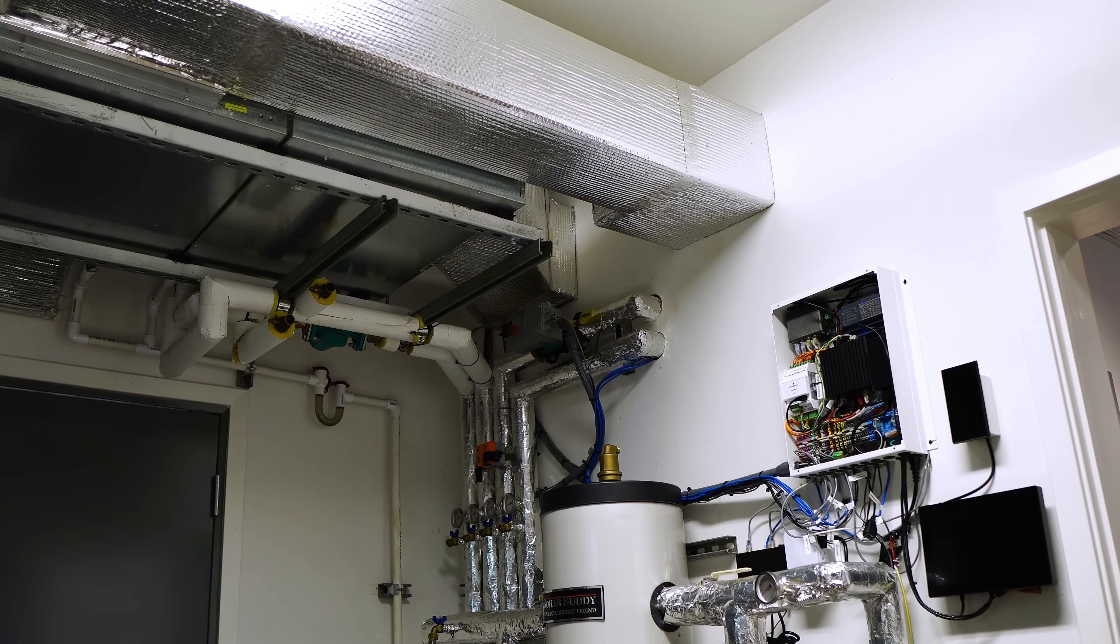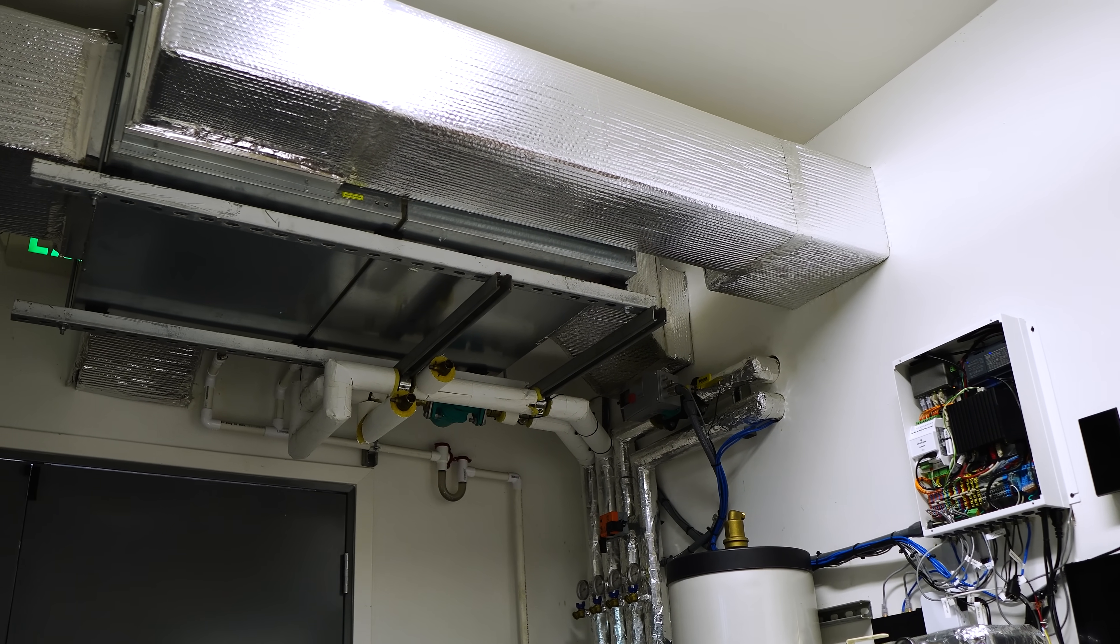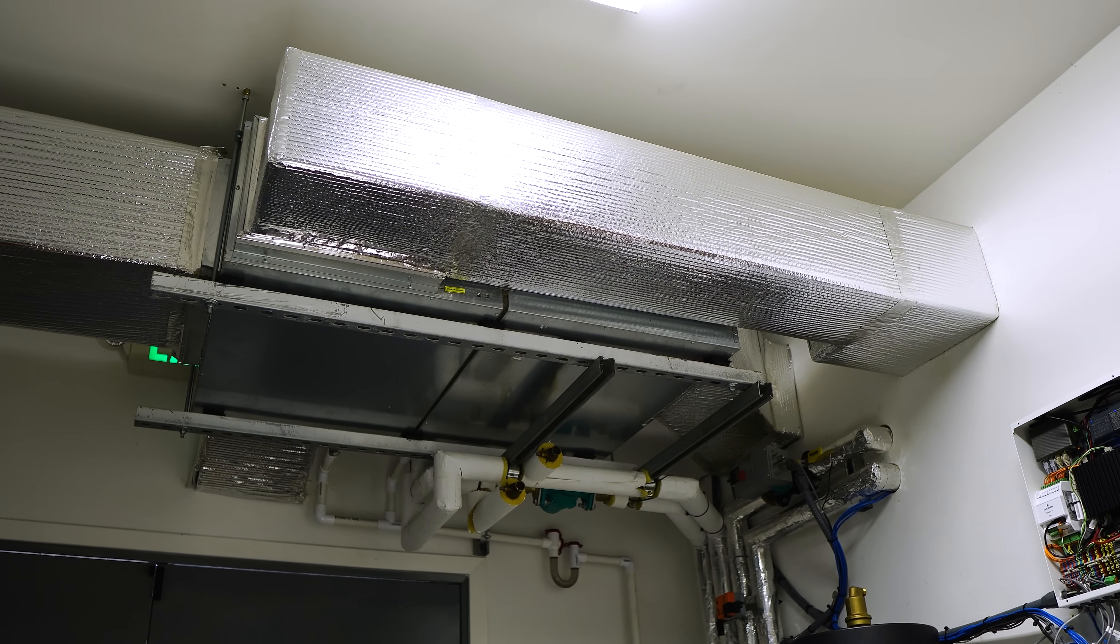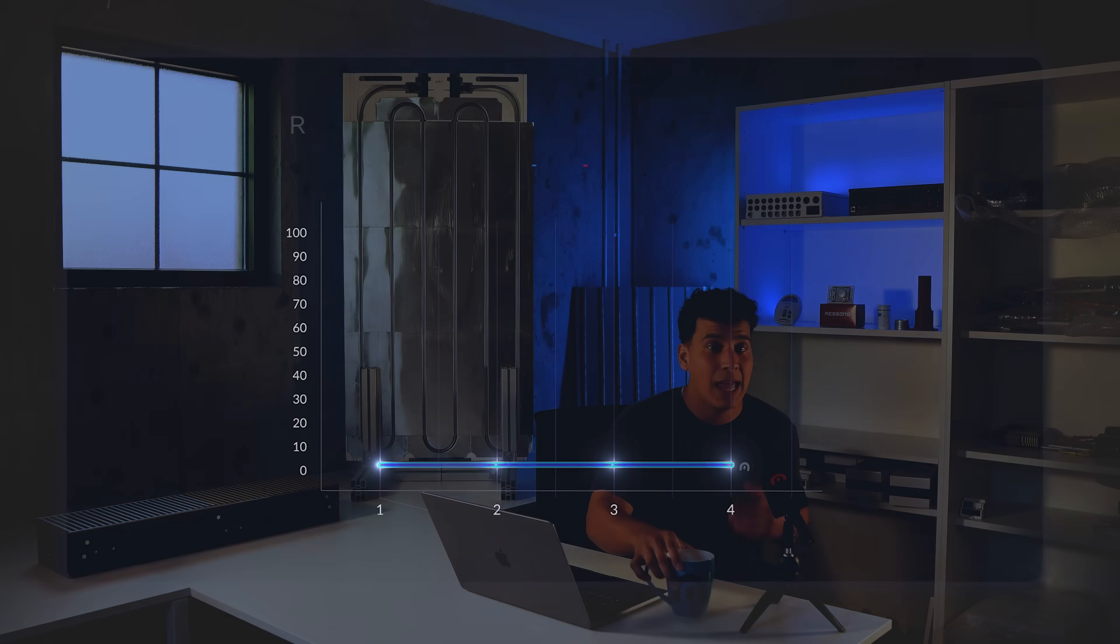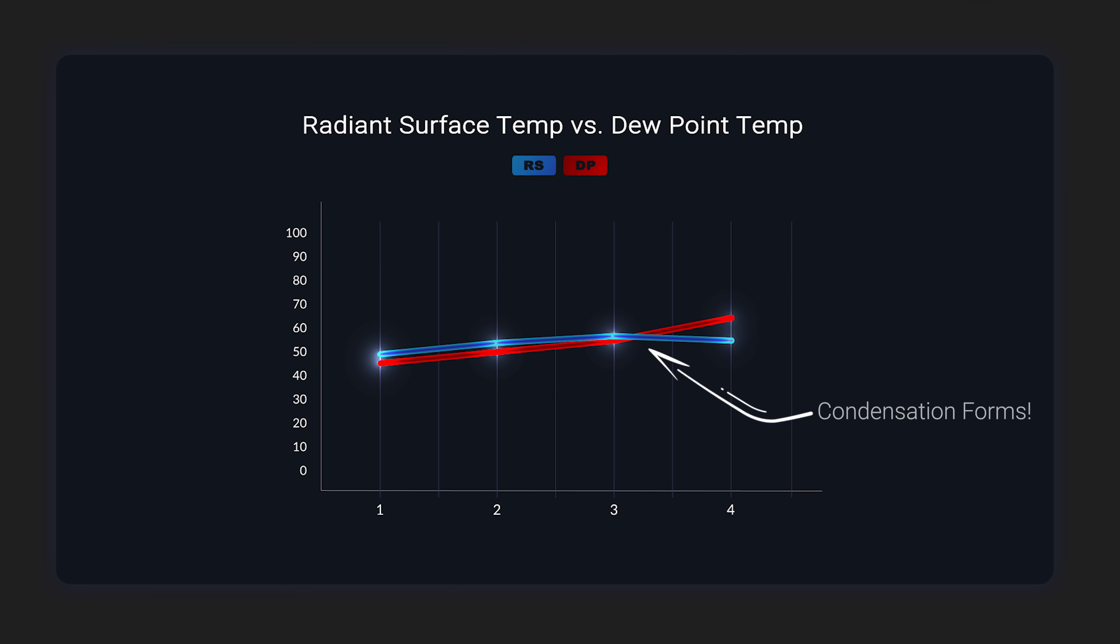And so that's another benefit of a hydronic system is you can really choose where you're sending the heat or cooling at any given time. Additionally, you can incorporate dehumidifiers. Those are really good and a big friend to radiant cooling systems because radiant cooling is a battle between the radiant surface temperature and the dew point temperature. If the radiant surface temperature falls below the dew point, condensation is going to form just like it does on the outside of a cold glass. And when we're providing radiant cooling, we need to avoid that. We can't have water forming on the ceiling or floors.